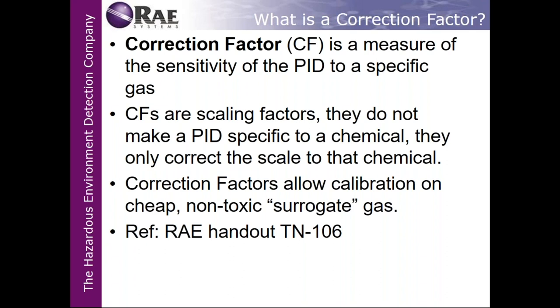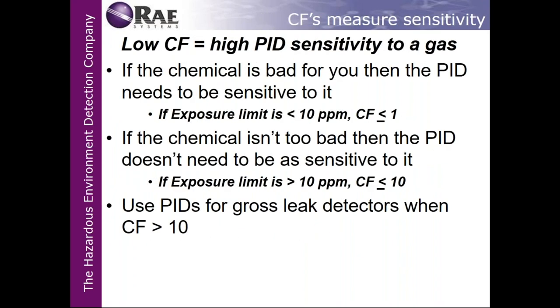But if you're in a manufacturing process, for instance a glue factory where you're going to be working with acetone and MMA, you would be able to change the correction factor to that particular VOC and measure it one-to-one. Low correction factors equal high PID sensitivity to a gas. So if I tell you that an IE is 9.07, I can tell you immediately that it's going to get a hit with your monitor, especially with a 10.6 lamp. If the chemical is bad for you, then a PID needs to be sensitive to it. If the chemical isn't too bad, then a PID doesn't need to be as sensitive for that particular application.